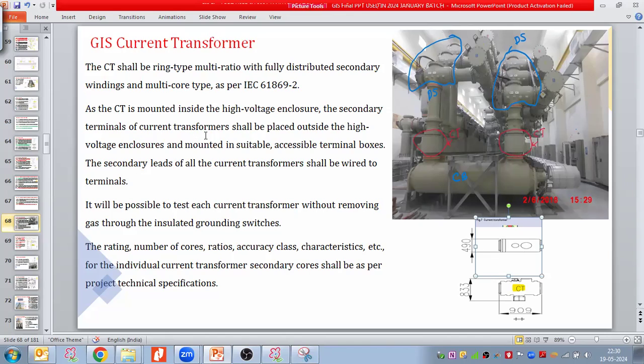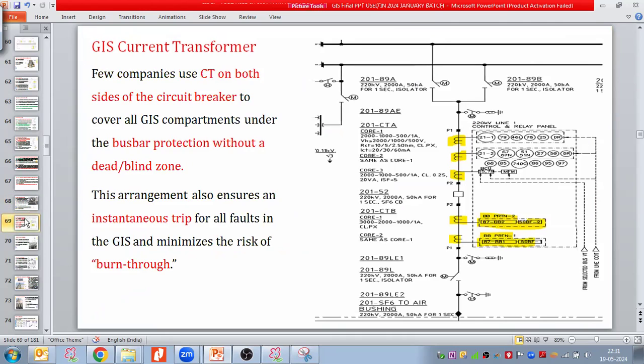The secondary terminals of the CT shall be placed outside the high voltage enclosure and mounted in suitable accessible terminal boxes. The secondary leads of all the CTs shall be wired to terminals. It will be possible to test each CT without removing gas, through the insulating grounded switch, the insulating link that we have discussed. The rating, number of cores, ratio, and class characteristics for the individual CT secondary cores shall be as per the project technical specifications. So according to that we have to take the CT rating.